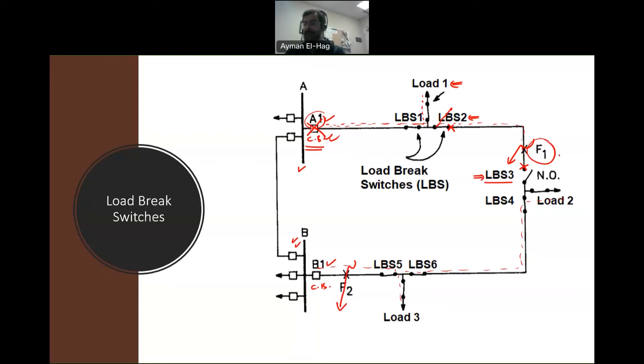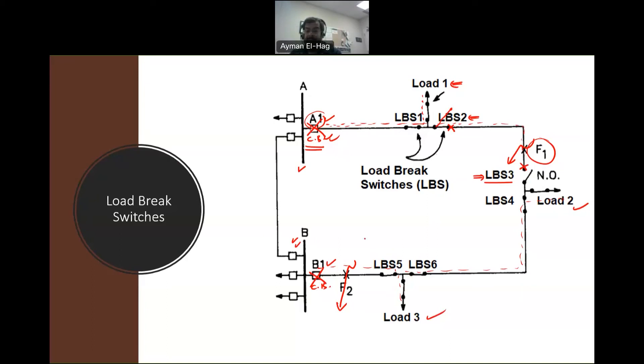Let's see another scenario: a fault at F2. Since LBS3 is normally open, bus A does not see this fault. Only circuit breaker B1 sees the fault and opens to clear it. The fault is now isolated from both sides. However, load 2 and load 3 now have no power. To isolate the fault properly, we open the normally closed LBS5 so the fault is isolated from both the circuit breaker side and the load break switch side.